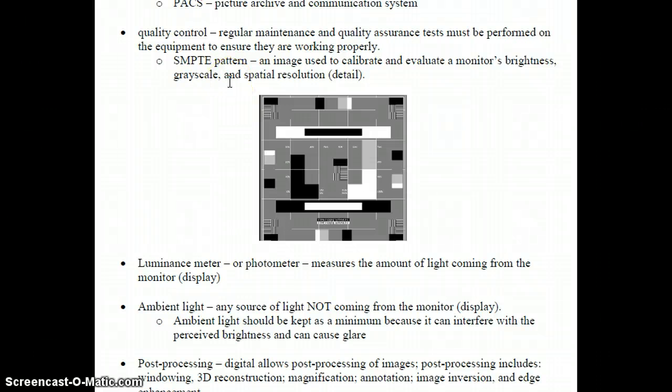Mainly the display monitor. We have this SMPTE pattern, and this is what it looks like. It's an image, and it's used to calibrate and evaluate the monitor's brightness, grayscale, and also the spatial resolution, which means detail. So in the digital world, the word detail is spatial resolution. This test pattern is what the medical physicist would use to calibrate the display or the monitor.